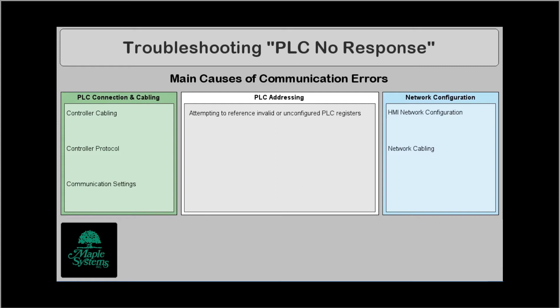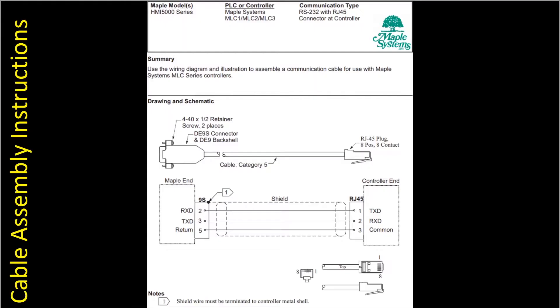Now when we look at the cabling issues first thing that we will recommend is that you go and review our cable assembly instructions. For example I have one showing here of the HMI 5000 series connecting to a Maple Systems MLC using RS232 cable with RJ45 connector and there you can see the diagram with the pinouts. So when you're looking at your cable for communication make sure to check the pinouts. Check continuity if you've built it yourself or you can purchase a cable from us and we can also build you a custom cable for your controller.